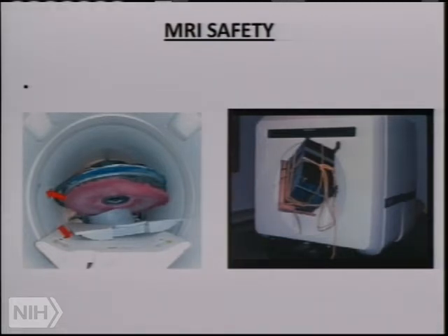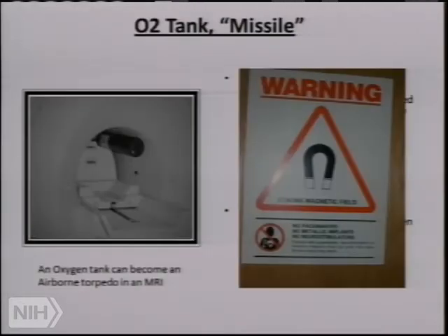There's a cabinet that got sucked in. It's a metal cabinet. Not a good idea. And perhaps one of the saddest things is when an oxygen tank gets brought into the room to ostensibly help a patient, it essentially becomes an airborne torpedo that can kill a patient if they happen to be in the scanner at the same time. So take this stuff very, very seriously.